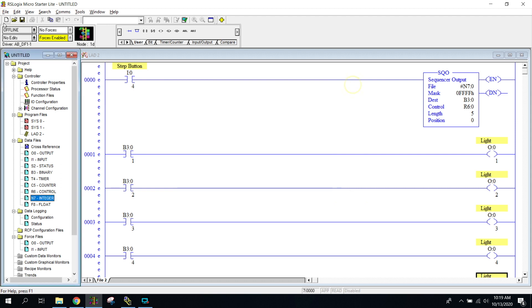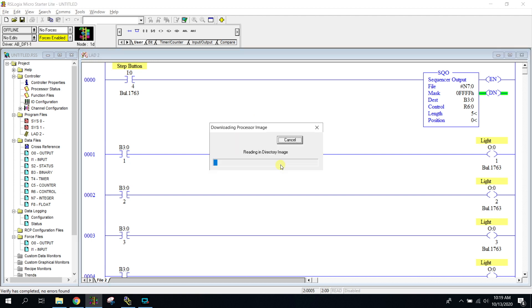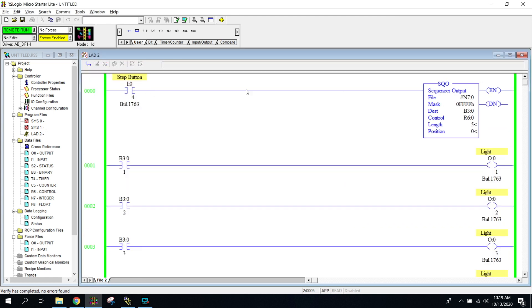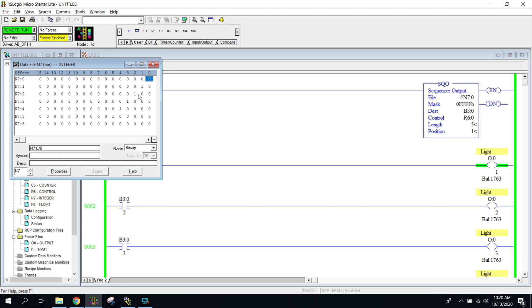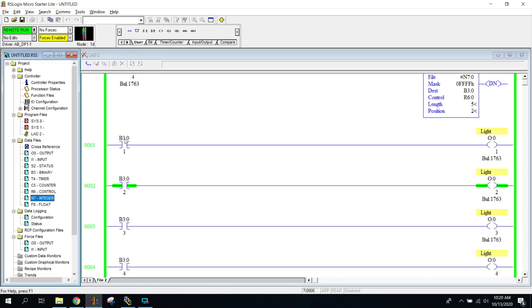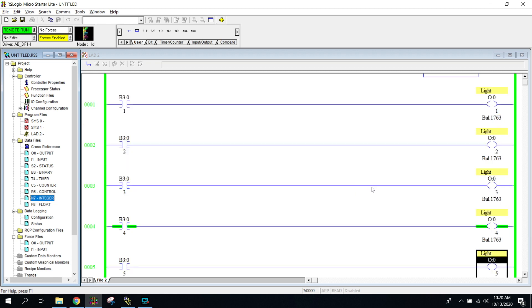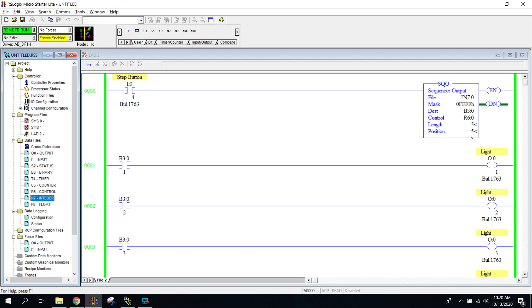I'm going to download our program and then press the button. Right now it's in position zero, but it will never go back to zero after this first time. I press the button — notice it's gone to position one, bit B3:1 is now turned on, and my light is on. As I press the button again, the next bit turns on, and the previous one turns off because in step two, that bit is no longer turned on. I keep rolling through all the steps. Now I'm on step five — I press the button one more time and it immediately goes back to step one, turning my first light back on.